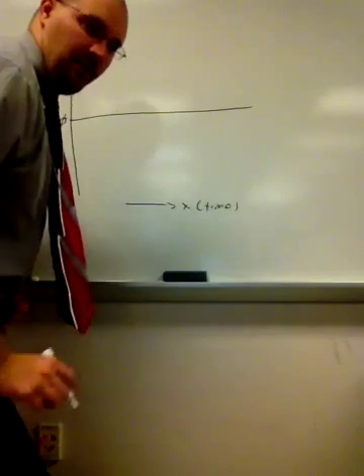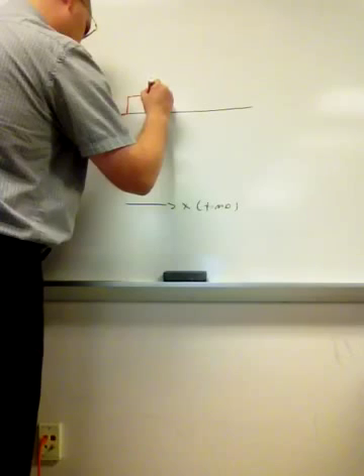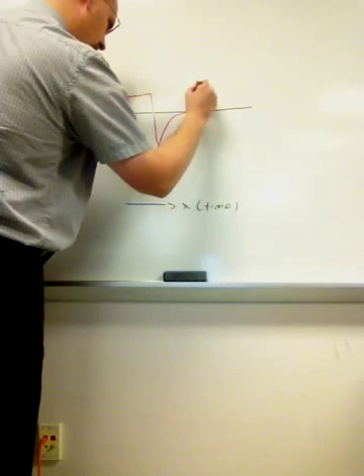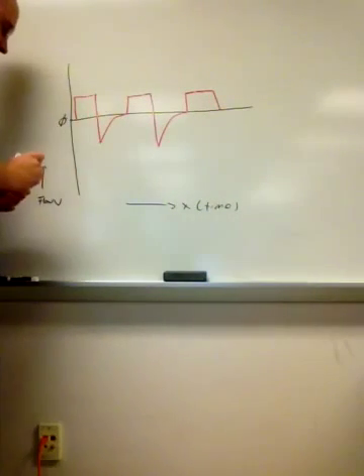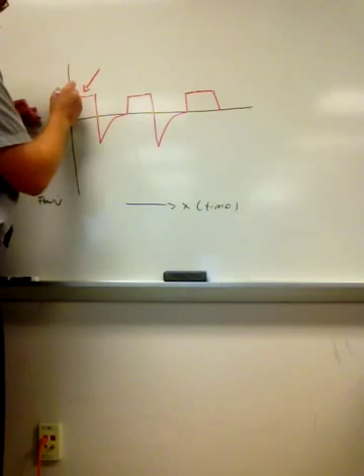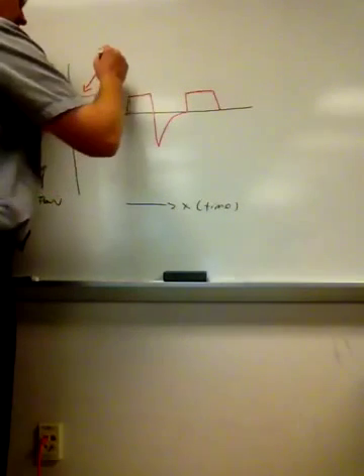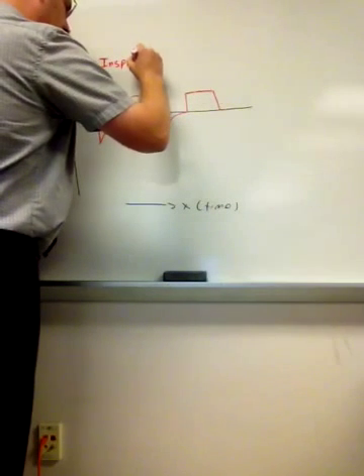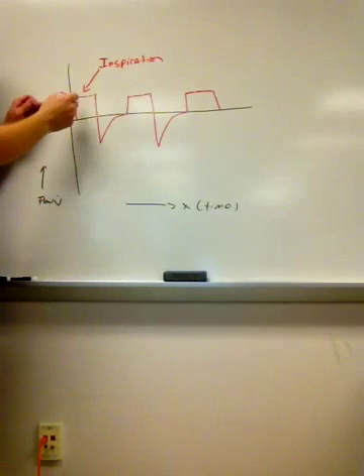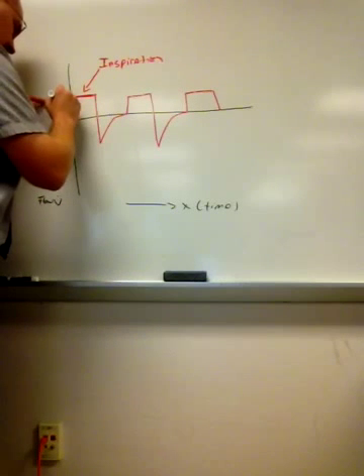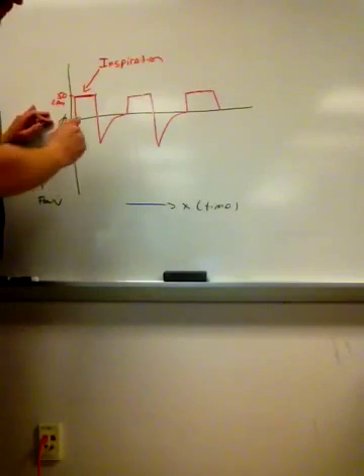Let's dissect this a little bit. I'll show you a real common graphic that we see with flow and make some sense of it here. You'll commonly see something that looks like this. So above the baseline here, positive numbers. Let's say that this is 50 liters per minute right here. This is all inspiration. So this is the ventilator delivering gas into the patient. In this case, this right here is at that 50 liter per minute mark. We would call that the peak flow, the peak flow rate.